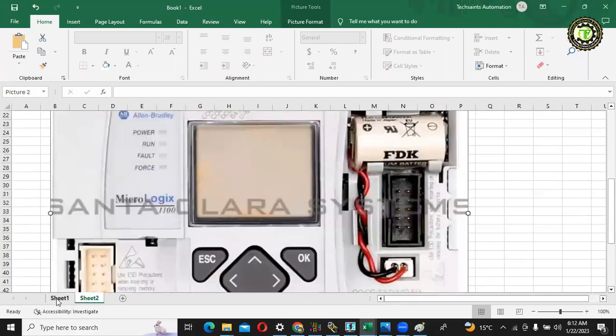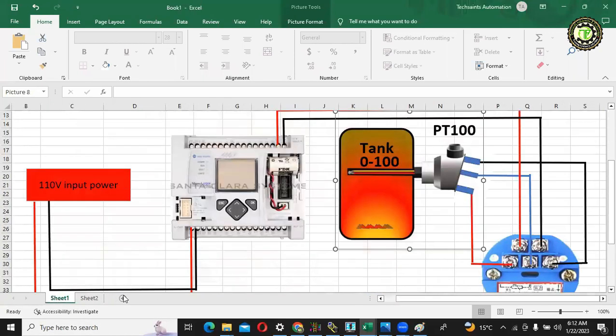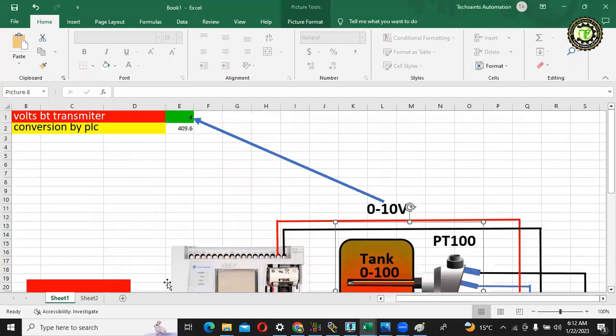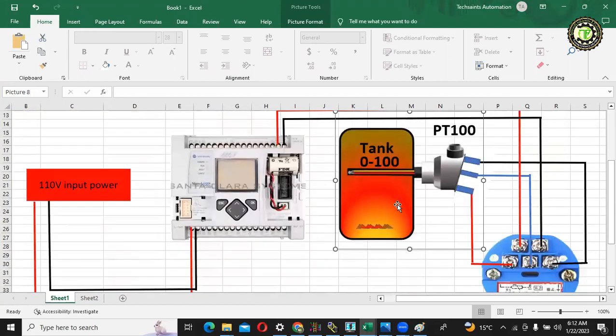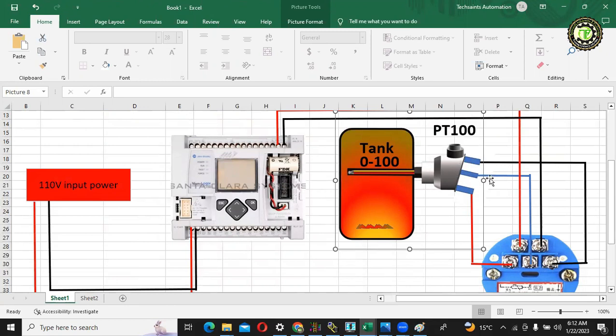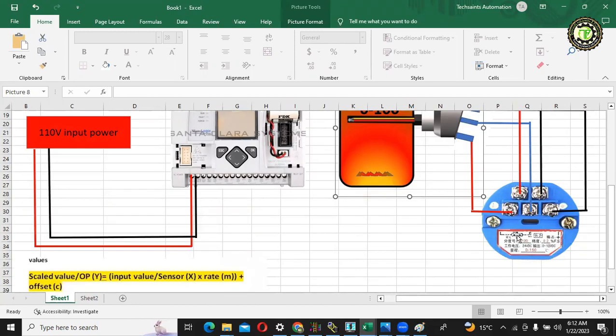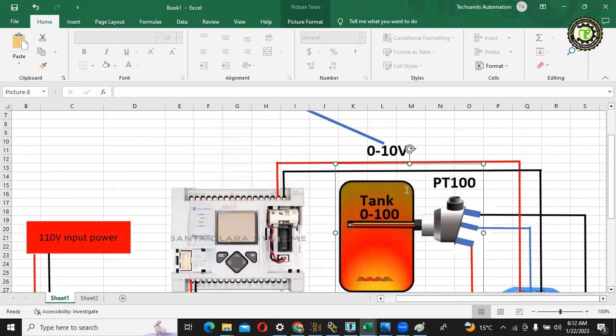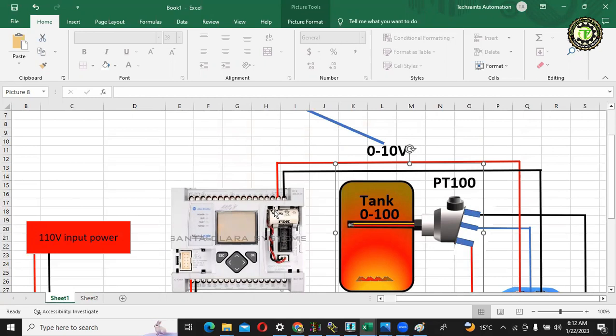I am now going to show you the connections. As you can see, this is my PT100. This PT100 will convert this temperature into resistance, and then this transmitter will convert this resistance into 0 to 10 volt. This 0 to 10 volt signal will go to the PLC analog input 1.